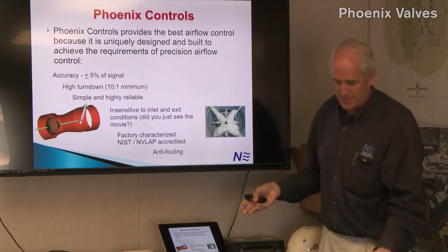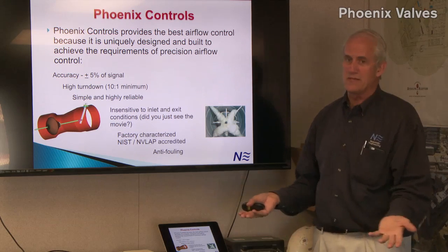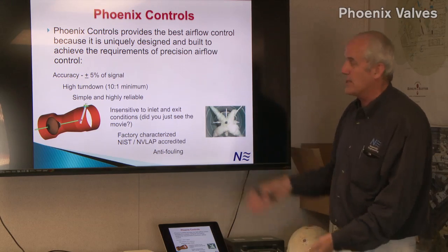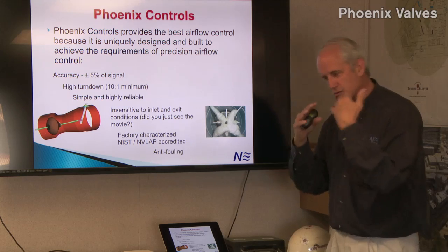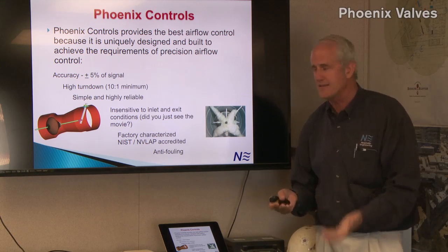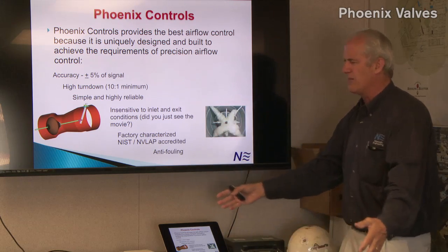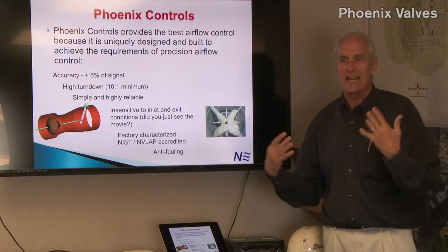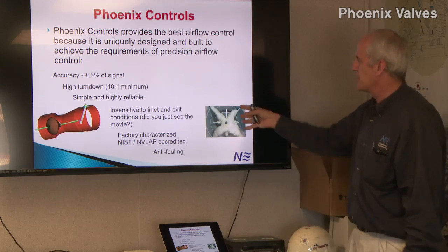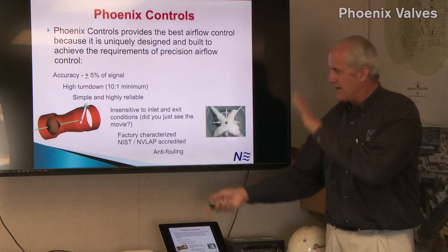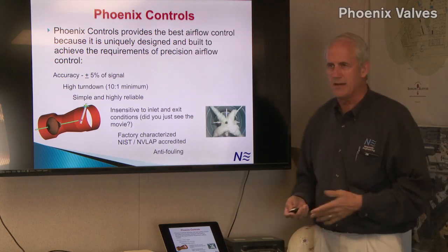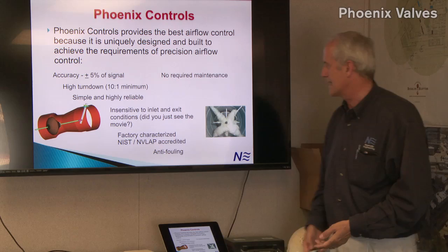So we went to the rooms and we said, by the way, every one of these rooms is still every bit as negative, but the front end with their air monitoring stations was reporting the room as positive because they were no longer measuring the exhaust that was actually there. So measuring has problems. Phoenix valve meters, it doesn't measure. We're going to continue to give you good control even if you get stuff like that going on.